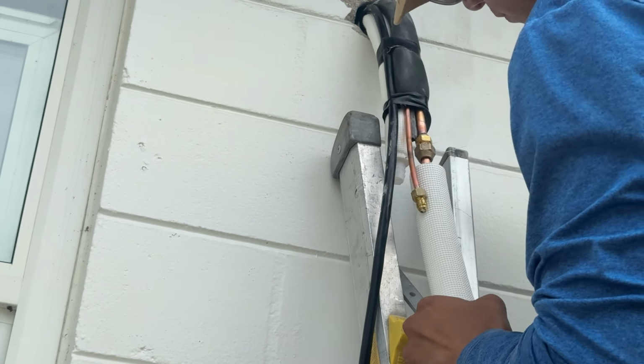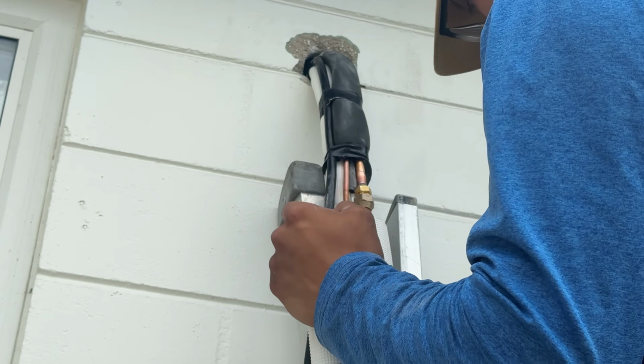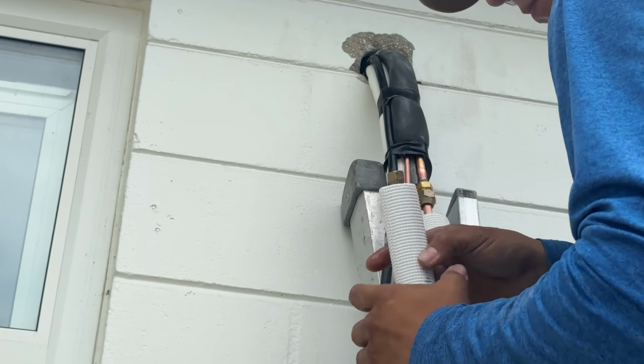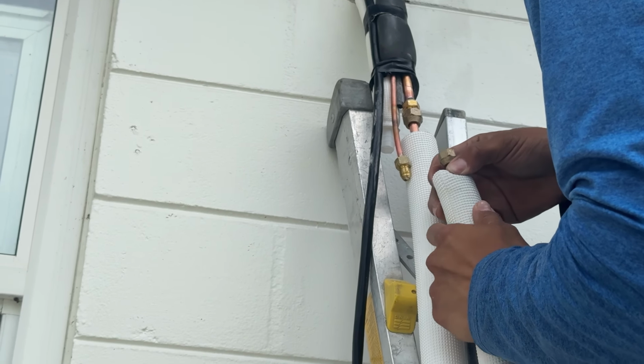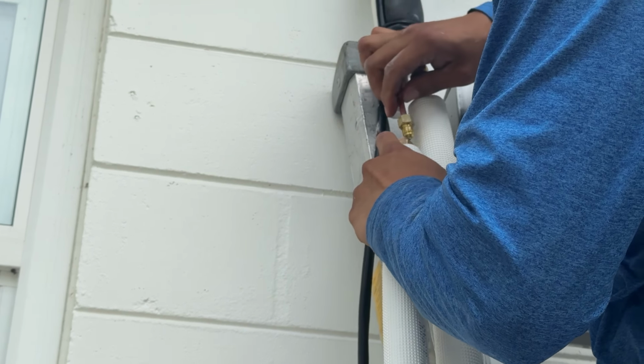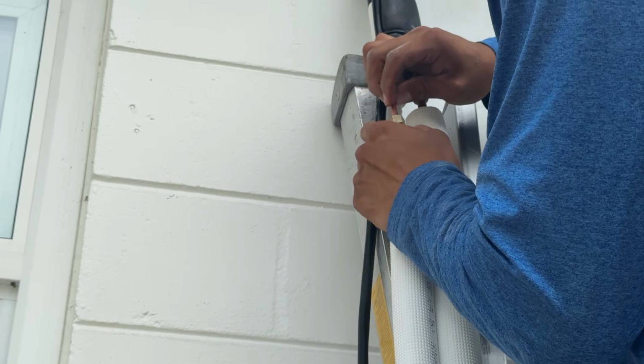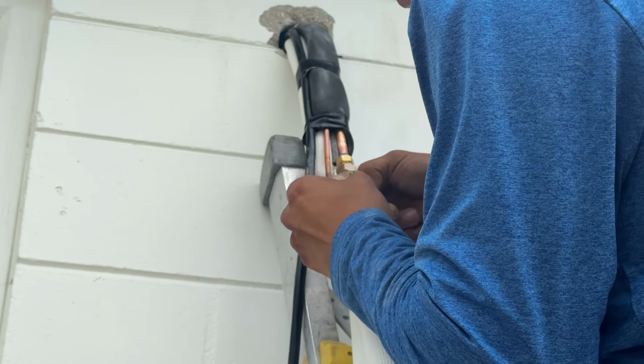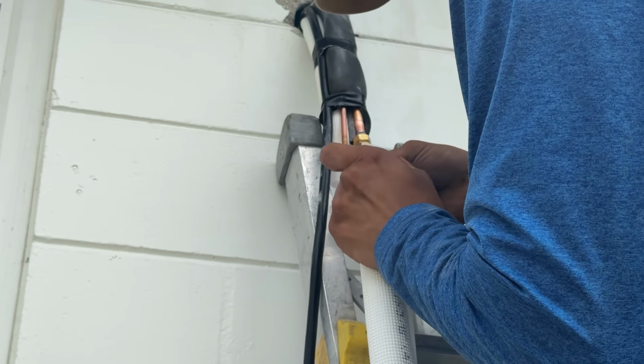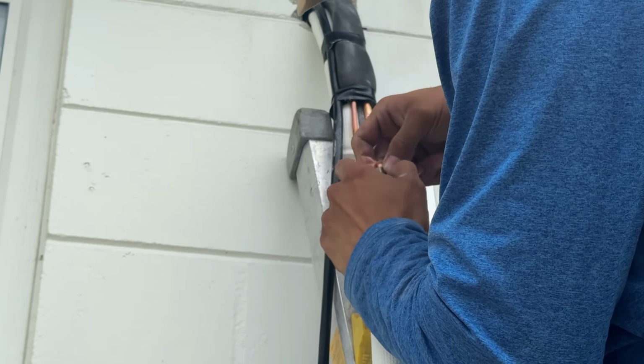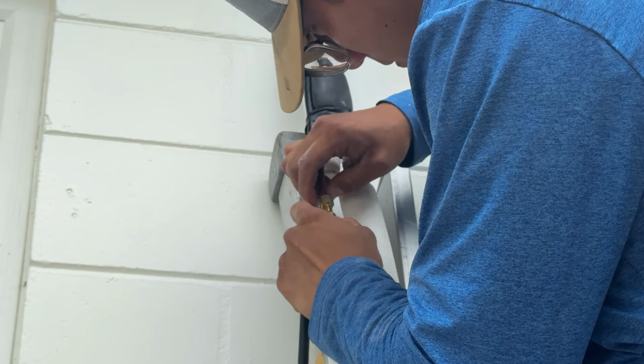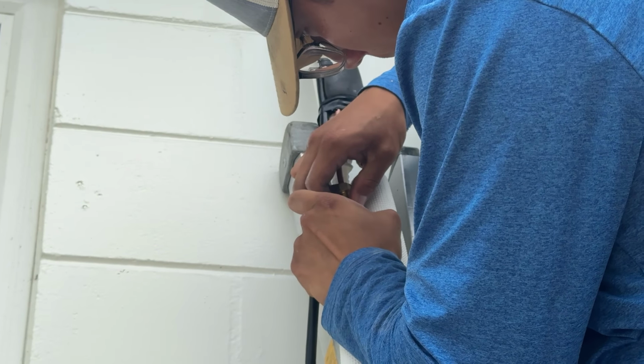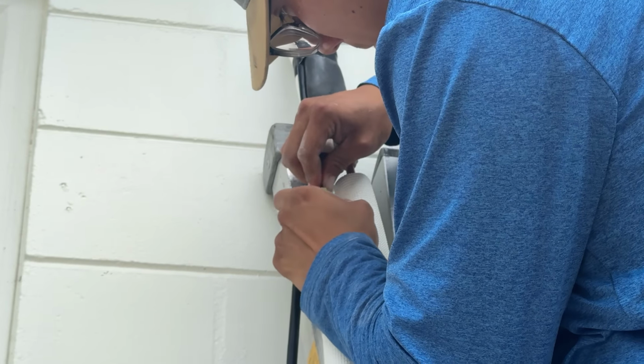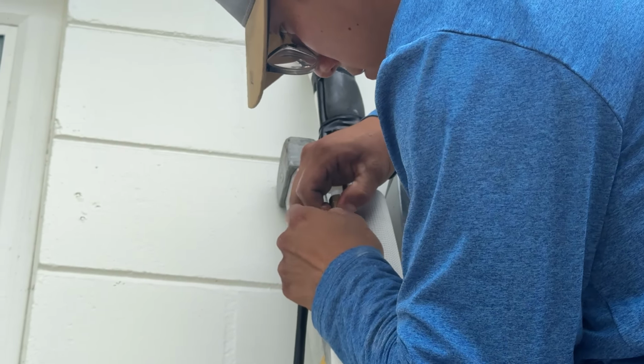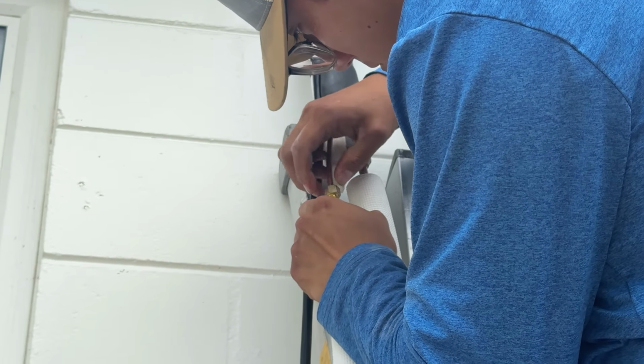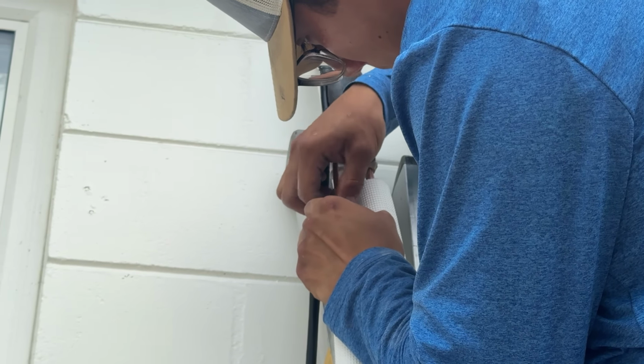I'm going to pass him the quarter inch now. Whenever you run lines, I don't actually use Nylog. Some manufacturers don't like it, and they'll void a warranty. Really, listen, I'm not worried about warranties on HVAC equipment, but I don't like anything on that face. Gotcha, but to each his own. It's made by a great manufacturer, Refrigeration Technologies. They make a lot of other cool products. But one thing I would never do is put one of those purple gaskets they do sell. You see them at some supply house counters and things like that. Yeah, I would not use that. You don't need a gasket there. You have a perfectly machined connection, a flare joint. Not necessary.